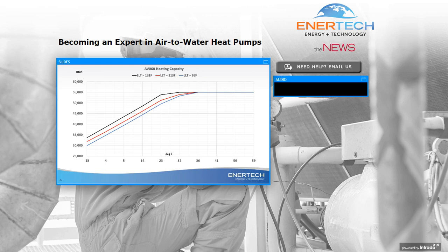When you look at specific numbers, this happens to be the 5-ton advantage air-to-water heat pump. We can then start dialing in on water temperatures. Of course, the best system is going to be the system that uses the lowest water temperature. That's why radiant floor works so well. The lower the water temperature of the heat pump, the higher the COP. And the same goes with designing any system, whether it's an air to water, whether it's a water to water. We want to try to design that system with the lowest possible water temperatures.